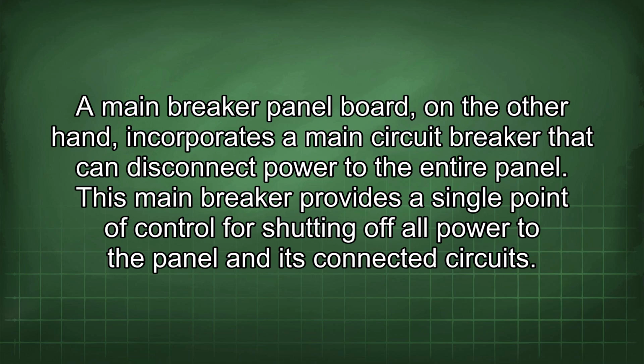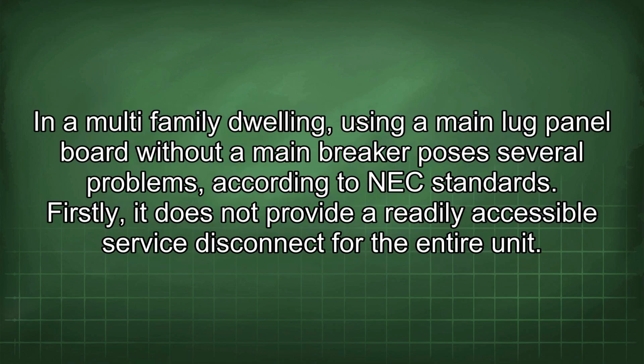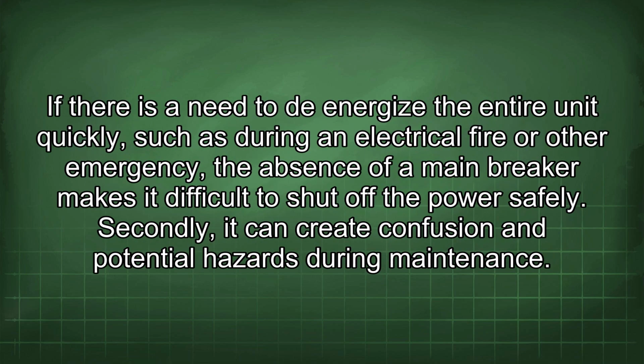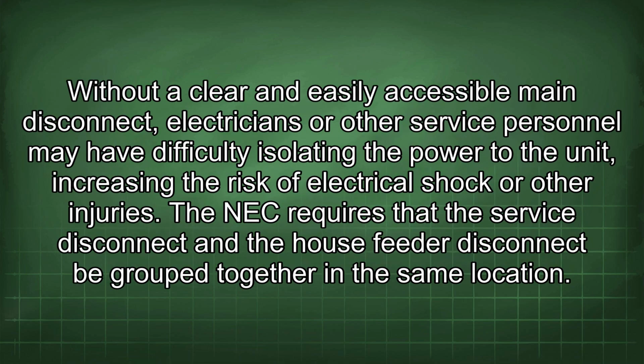In a multi-family dwelling, using a main lug panel board without a main breaker poses several problems according to NEC standards. Firstly, it does not provide a readily accessible service disconnect for the entire unit. If there is a need to de-energize the entire unit quickly, such as during an electrical fire or other emergency, the absence of a main breaker makes it difficult to shut off the power safely. Secondly, it can create confusion and potential hazards during maintenance. Without a clear and easily accessible main disconnect, electricians or other service personnel may have difficulty isolating the power to the unit, increasing the risk of electrical shock or other injuries.